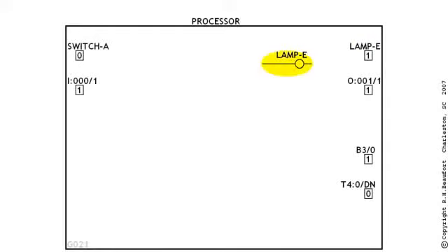Now, just a few milliseconds later, let's say that the processor comes back around to the same OTE again. But this time around, something has changed the run conditions, and so now we've got false logic coming in. According to the rule, the processor has to go write a 0. The processor follows the address to the bit named lamp E and writes a 0 into the box. And now the processor is finished with the OTE for this pass through the program. And it really is just that simple.